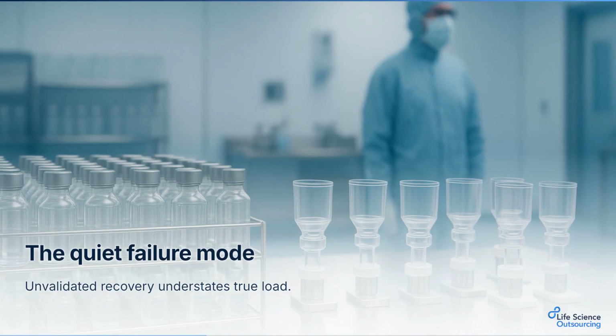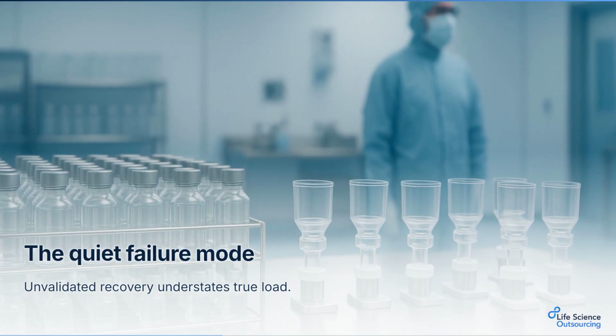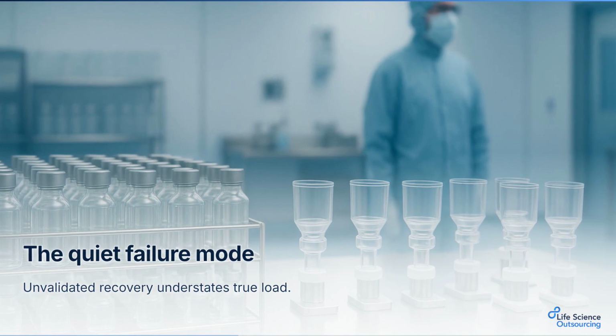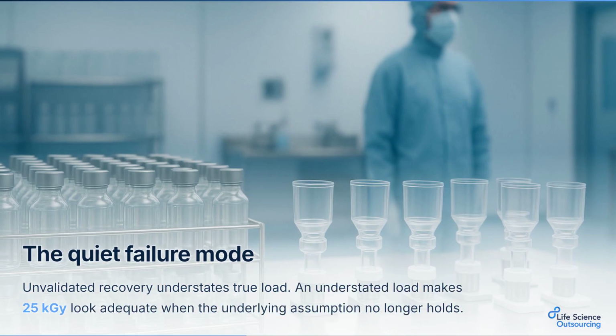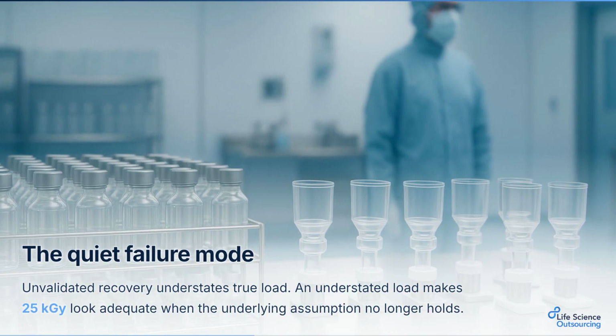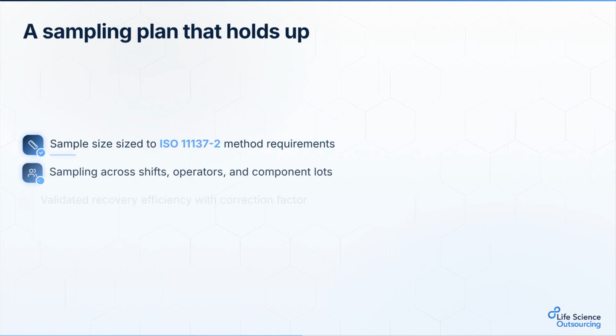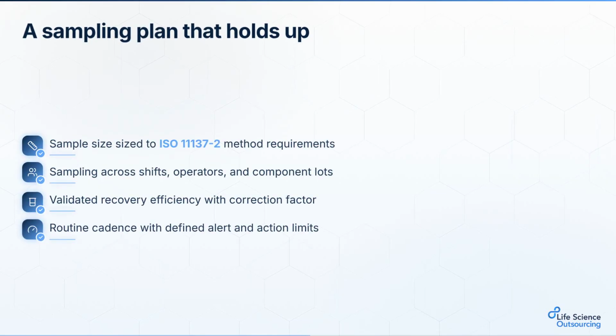Recovery efficiency is where programs quietly go wrong. No extraction pulls 100% of organisms off a device. ISO 11737-1 requires you to validate recovery before routine testing, because an understated bioburden makes a dose look adequate when it may not be.